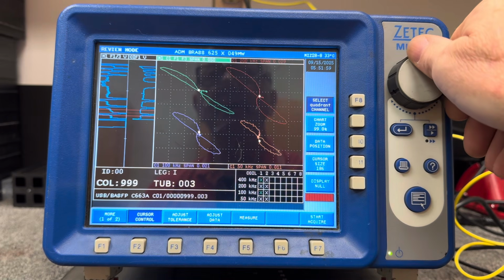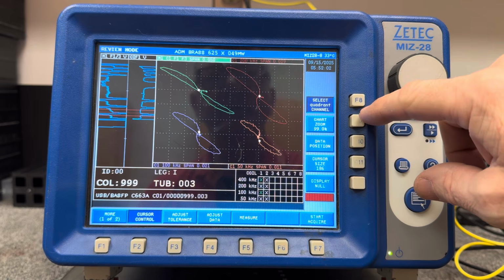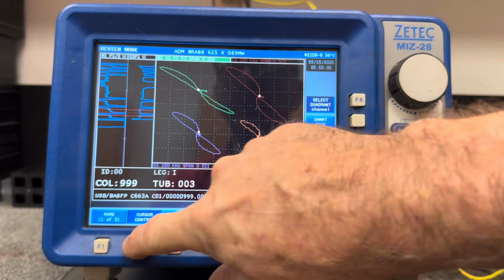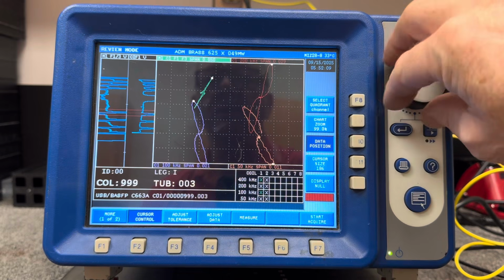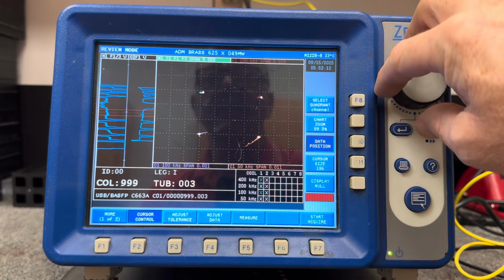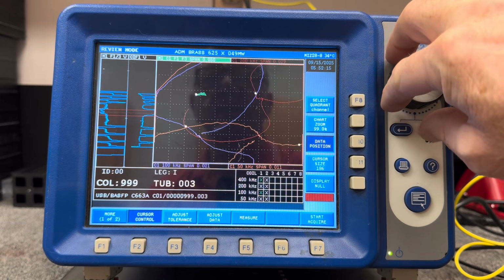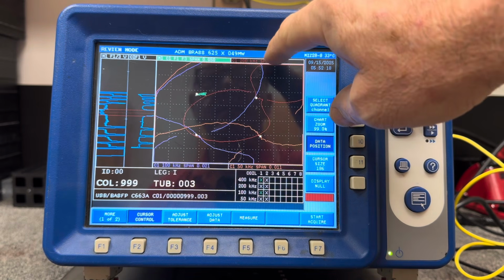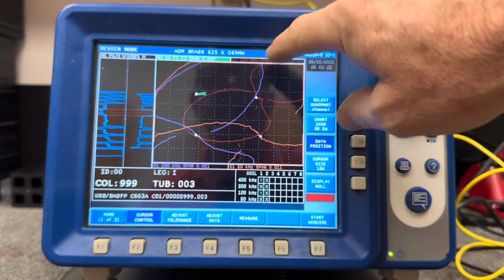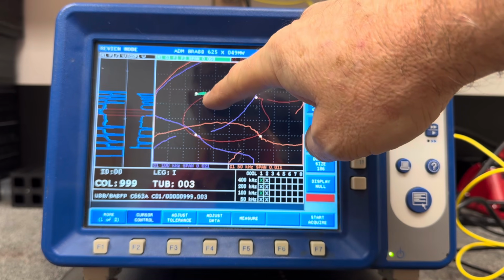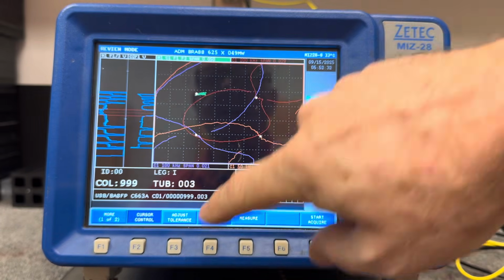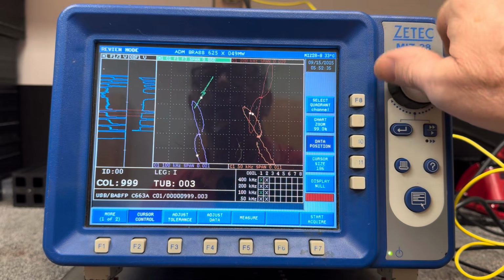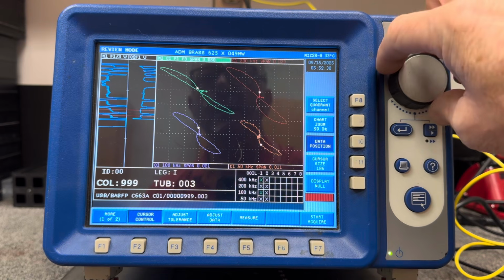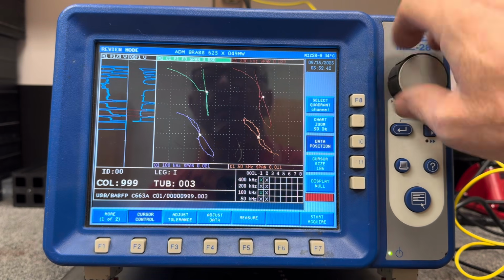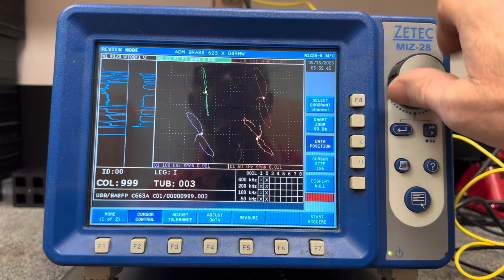which is right here. So obviously you can still see the support plates, but then when you go to the tube, you can still see the flaws, is what I meant to say. So right now we're on top of the tube support plate, and you notice 200 kilohertz, 100 kilohertz, 50 kilohertz, they all see the signal very prominently. But if you look at just the mix channel, the tube support plate is completely mixed out, yet you can still see all of your flaws on your mix. So when you're in your component and you're clicking through your support plates, you'll be able to find those little flaws underneath support plates, which is nice.